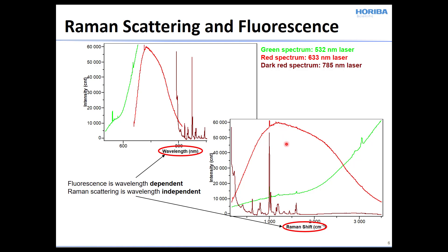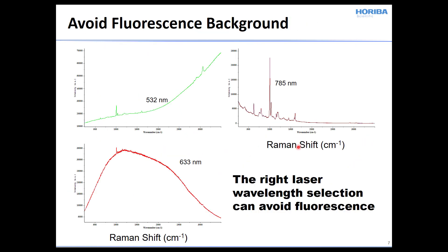And if the fluorescent intensity is so strong that the noise it generates can be comparable to that of the Raman scattering, which is an inherently weak phenomenon, then these bands that you see very nicely at 785 nanometer excitation are obscured. Certainly in the 633 nanometer excited spectrum, we only see the most intense peak, whereas all these other peaks are diminished and they're basically lost and buried in the noise. This is the problem with the fluorescence in acquiring Raman spectra.